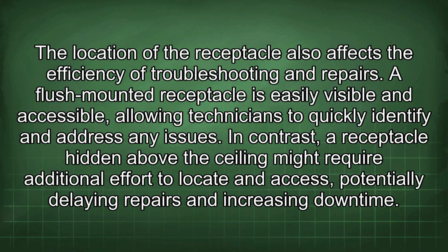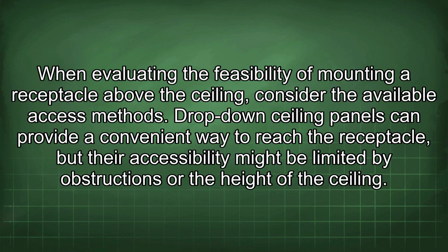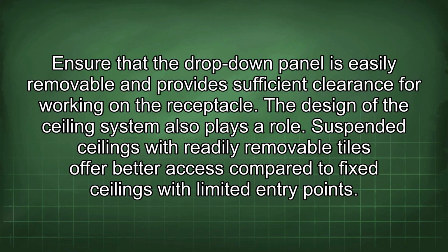The location of the receptacle also affects the efficiency of troubleshooting and repairs. A flush-mounted receptacle is easily visible and accessible, allowing technicians to quickly identify and address any issues. In contrast, a receptacle hidden above the ceiling might require additional effort to locate and access, potentially delaying repairs and increasing downtime. When evaluating the feasibility of mounting a receptacle above the ceiling, consider the available access methods. Drop-down ceiling panels can provide a convenient way to reach the receptacle, but their accessibility might be limited by obstructions or the height of the ceiling. Ensure that the drop-down panel is easily removable and provides sufficient clearance for working on the receptacle.